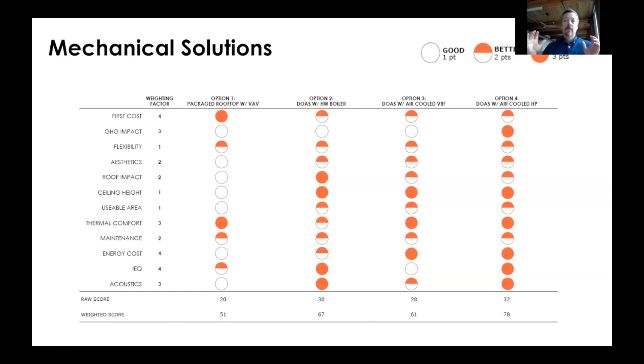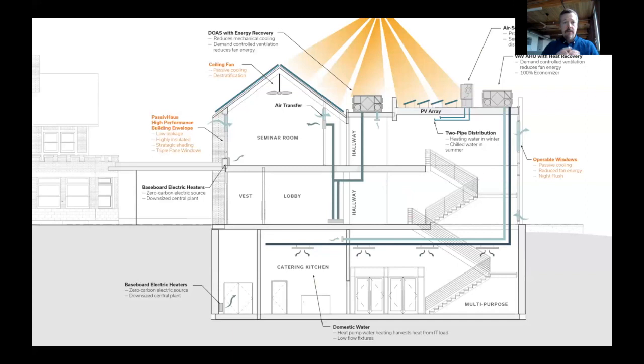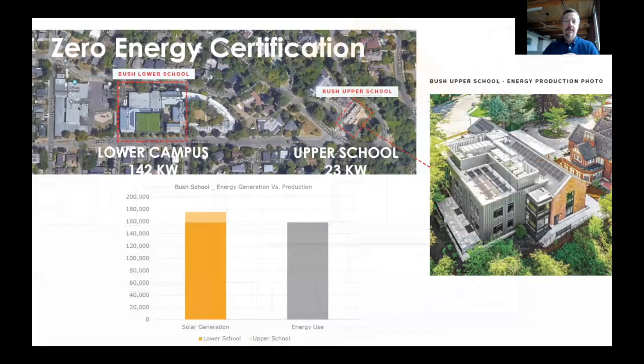So we pulled away from refrigerant-based distribution systems and tried to get a hydronic solution with a packaged heat pump instead of refrigerant lines throughout. We ended up with a DOAS with energy recovery and air source heat pumps on the roof, with a 2-pipe changeover system. If there are mechanical engineers or architects here, you may have had a 2-pipe changeover project go sideways. This comes back to needing truly integrated design to do that properly and avoid simultaneous loads and conditions in a building that would require both heating and cooling at the same time. So you have to think about design more than you would with a normal 4-pipe system.